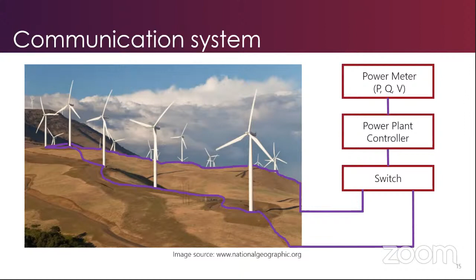So what happens if this communication system fails? Here's an example from a battery system that was initially designed assuming data transfer would be staged or staggered, not all at once. Unfortunately, the plant was reset entirely on a particular day, and it started sending and receiving commands almost simultaneously, overloading the communication network. As a result, the plant controller stopped communicating with the inverters charging the battery, and those inverters began tripping.